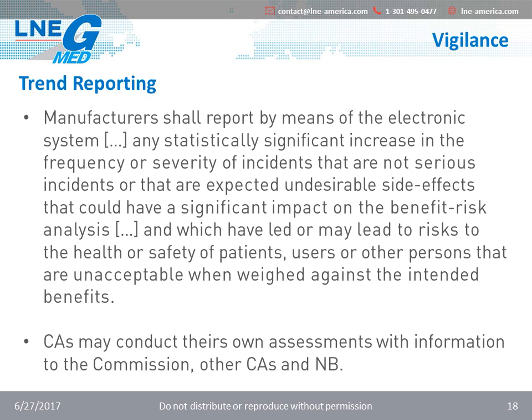The regulation is then introducing a new requirement related to trend reporting. For incidents that are not serious incidents covered by the previous article, manufacturers shall report using the electronic system any statistically significant increase in the frequency or severity of incidents that are not serious incidents or are expected undesirable side effects that could have a significant impact on the benefit-risk analysis, and which have led or may lead to risks to the health or safety of patients or users that are unacceptable when weighed against the intended benefits.